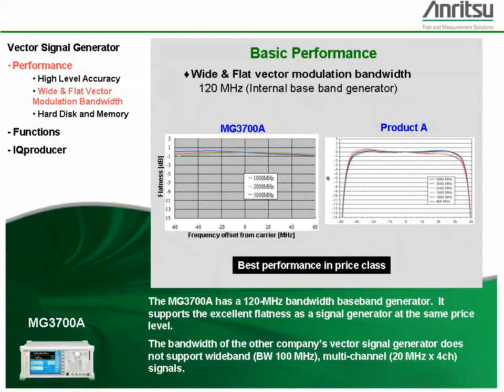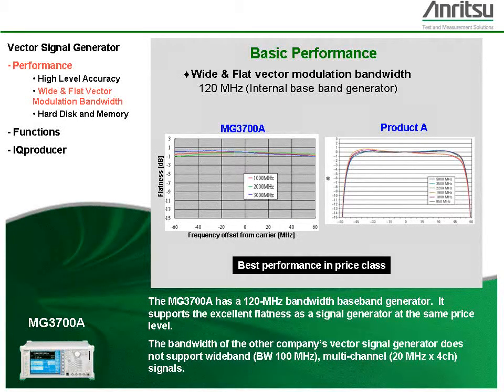The MG3700A has a 120 MHz bandwidth baseband generator. It supports the same excellent flatness as a signal generator at the same price level. The bandwidth of a general-purpose vector signal generator does not support wideband or multi-channel signals, such as bandwidths of 100 MHz or more and 20 MHz by 4 channels.